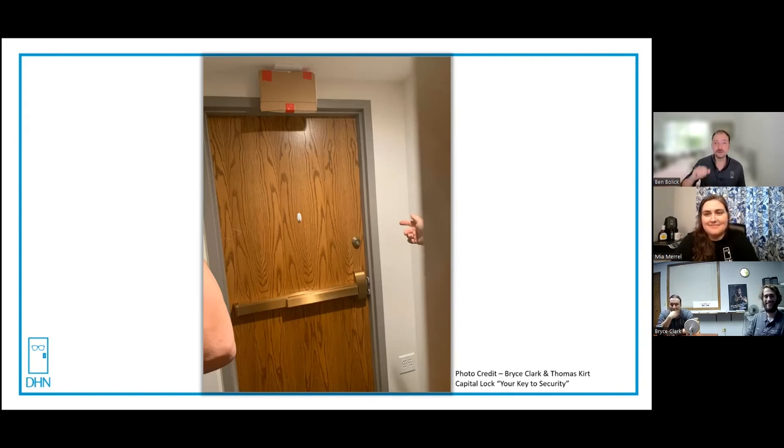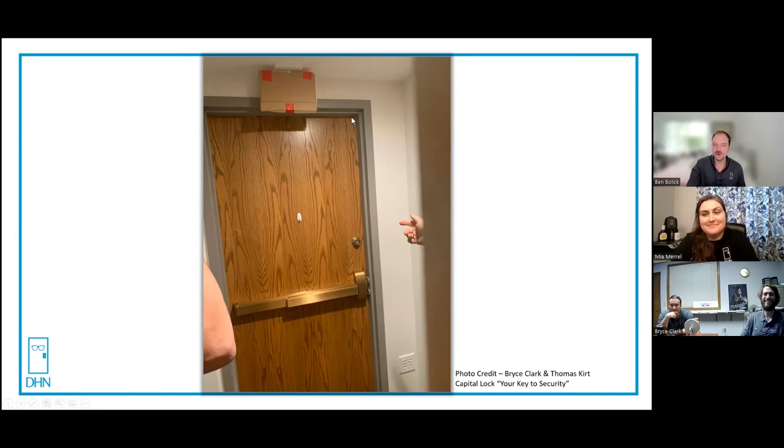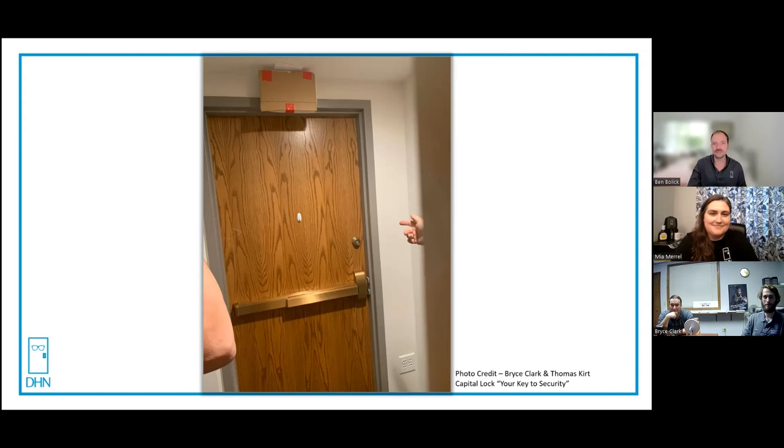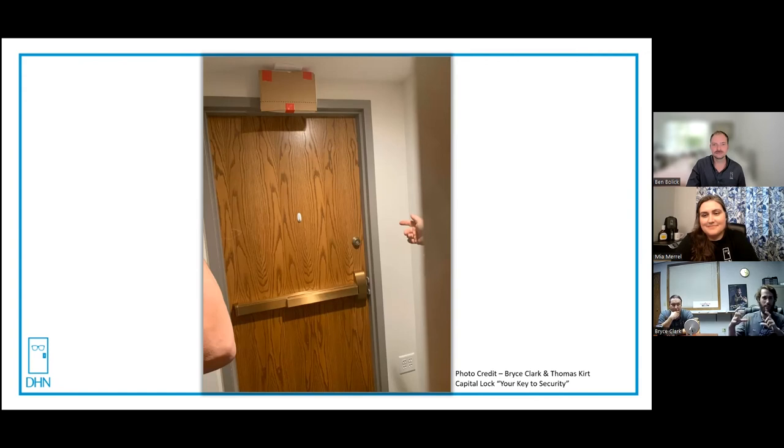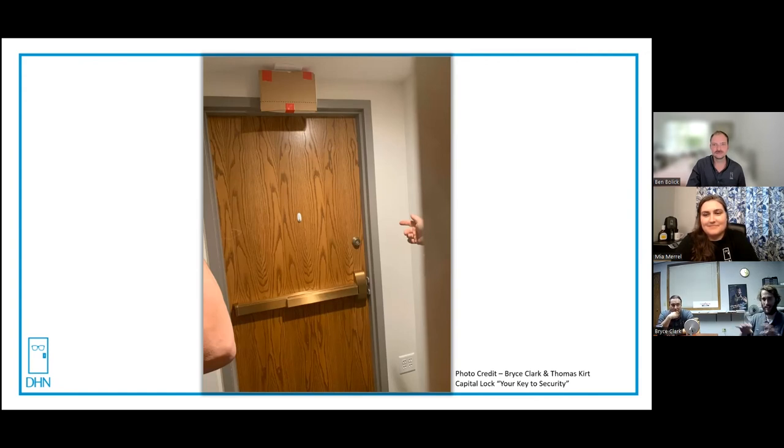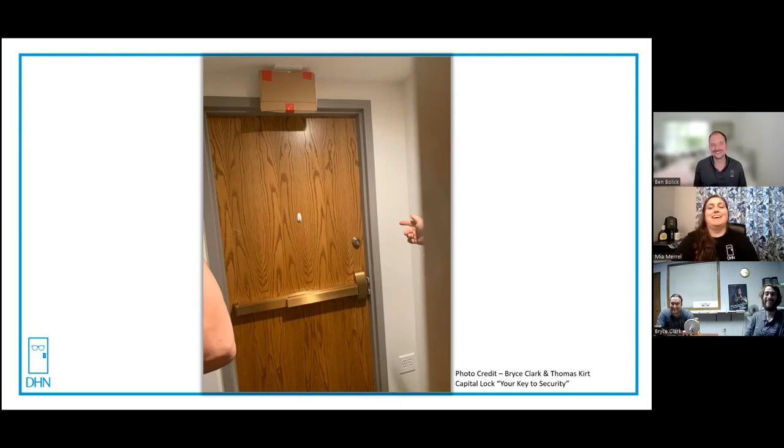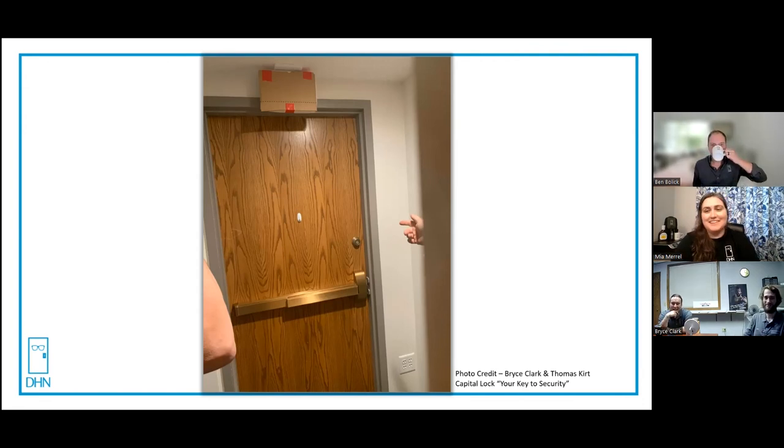Also, if they were removing this as an exit, that cardboard sign is not compliant either. You would still have to remove the sign and make sure all the signs leading down to this pathway is removed as well. And you would have to have another form of egress depending on the occupancy of the building as well. I heard that they replaced that piece of cardboard. They used to tape up different signs depending on what land they were in for Dungeons and Dragons. So, this is not the exit you're looking for. Exit, if you dare.